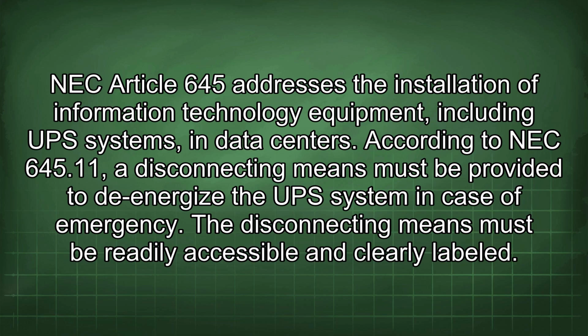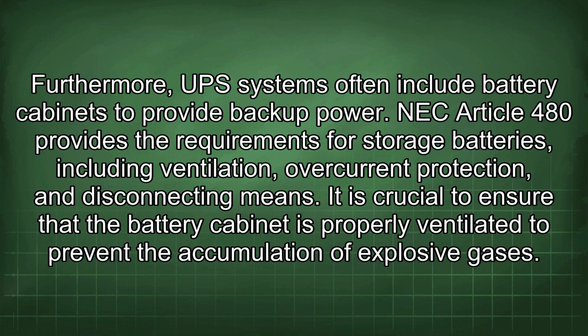According to NEC 645.11, a disconnecting means must be provided to de-energize the UPS system in case of emergency. The disconnecting means must be readily accessible and clearly labeled. Furthermore, UPS systems often include battery cabinets to provide backup power. NEC Article 480 provides the requirements for storage batteries, including ventilation, overcurrent protection, and disconnecting means.